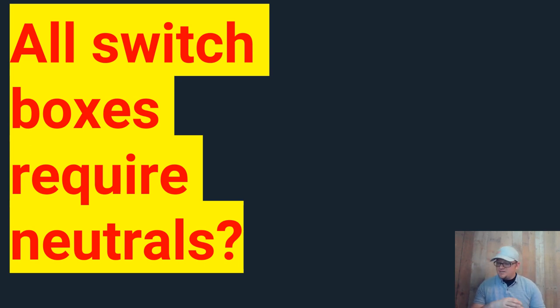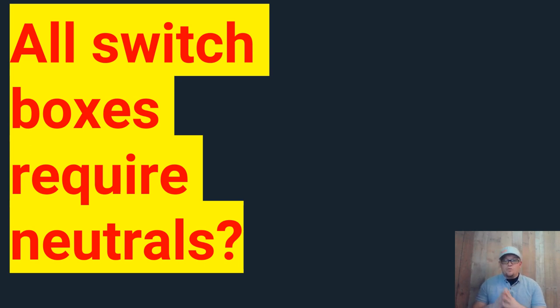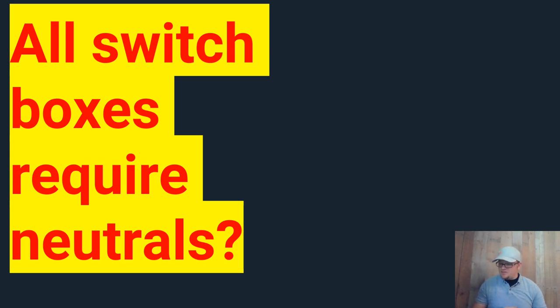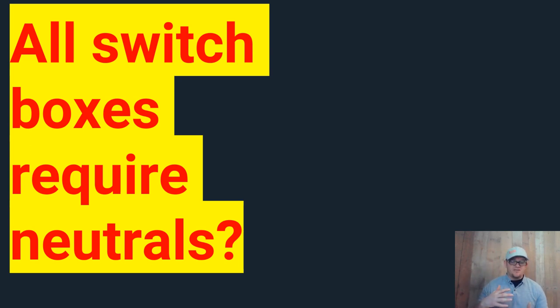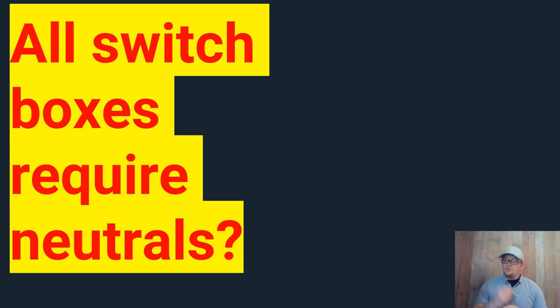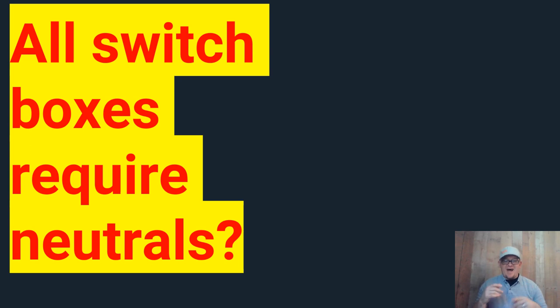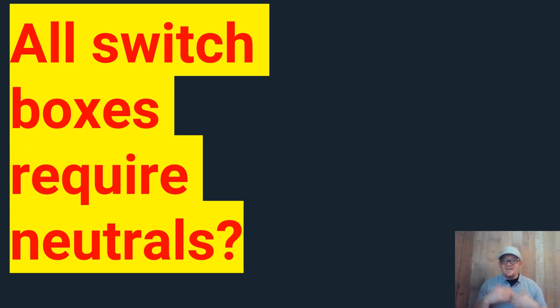The second point here is if the box or enclosure is accessible without damaging the finishing surface. So what it's saying here is that if I can fish a wire there later without damaging the surface, then I don't have to have a neutral inside that box. Well, let me ask you a question. If I'm doing a rewire on a house and I can fish a wire there one time, can I fish a wire there again? And the answer is yes.